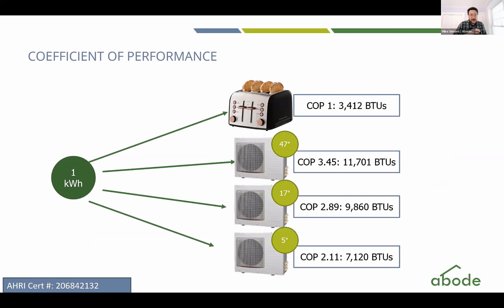One thing about coefficient of performance with heat pumps, though, is it's not always fixed. With the toaster oven, which has a coefficient of performance of 1, you put in 1 kilowatt hour of electricity and it's always going to put out 3,412 BTUs. With a heat pump, when it's warm outside, maybe it's 1 unit of electricity and nearly 12,000 BTUs worth of heat. But by the time it's 5 degrees outside, it may be 1 unit of electricity and just a little over 2 units of heat.